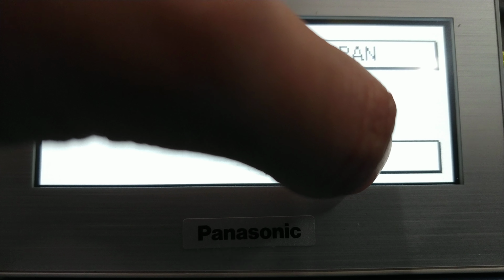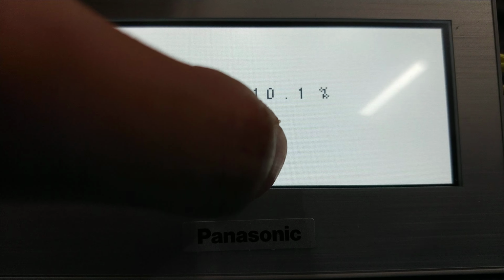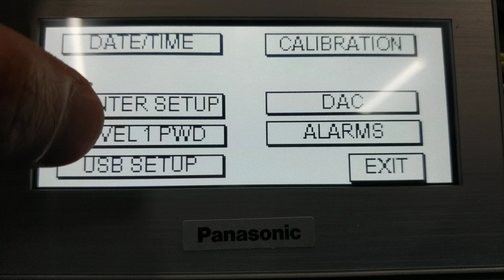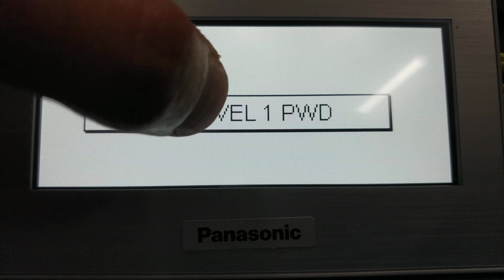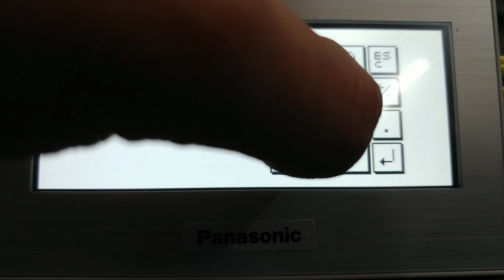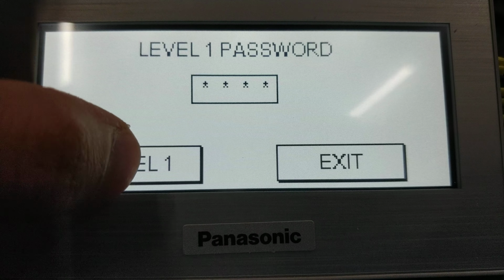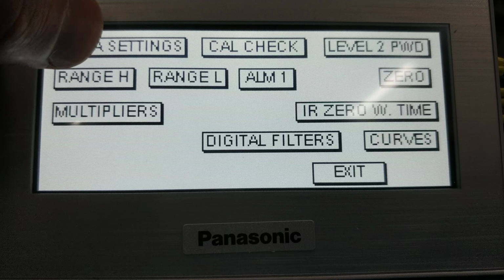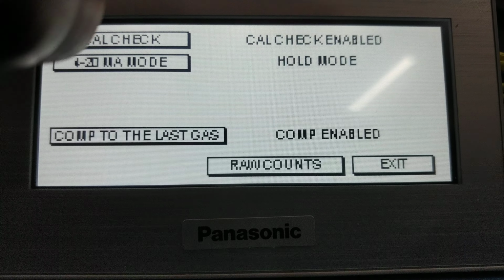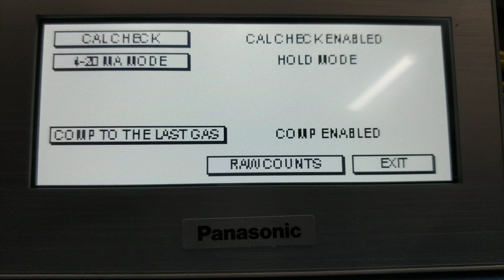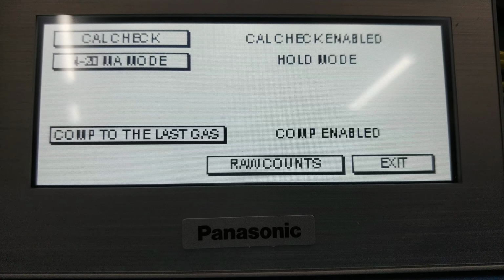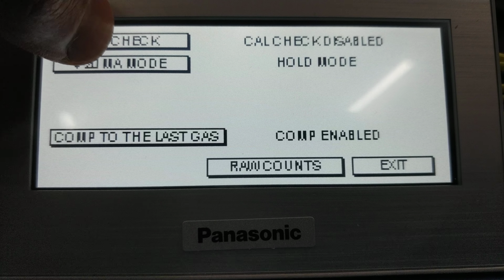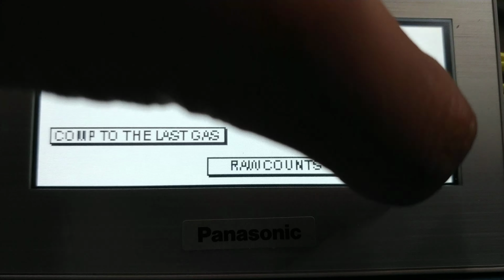So now that we did this, we want to do one more thing. We want to go back and make sure the cal check is disabled if we haven't already done so. Go to setup, level 1 password, to level 1, 270 is the password, level 1 again. So Nova settings now. And you see cal check is enabled right now. We want to make sure this is disabled for now. We're going to re-enable it once we're done all our calibration. So we're going to disable this. Let's disable. Exit. Exit. Exit.